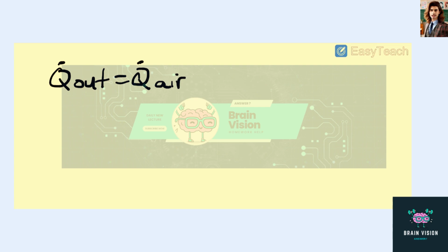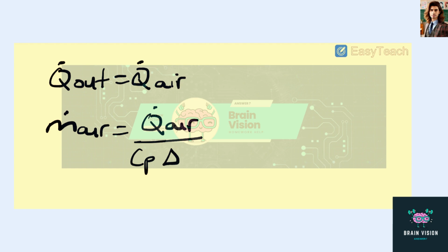And we can solve for the mass flow rate of the air first, by saying that m dot air is equal to Q dot air all over Cp delta T of the air. Now, we can look up in the table that the Cp of air is 0.24 BTU per pound mass degree Fahrenheit, and our delta T is given as 10 degrees Fahrenheit, because that's given to us in the problem statement.